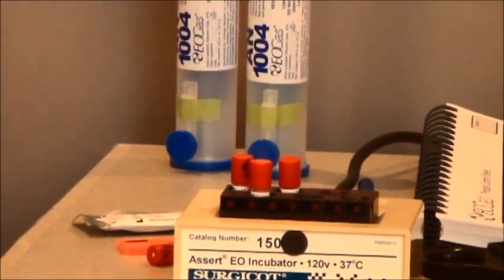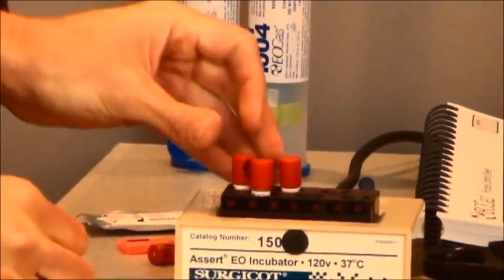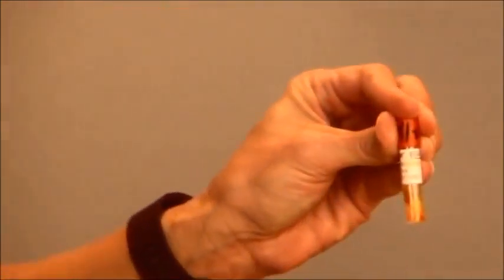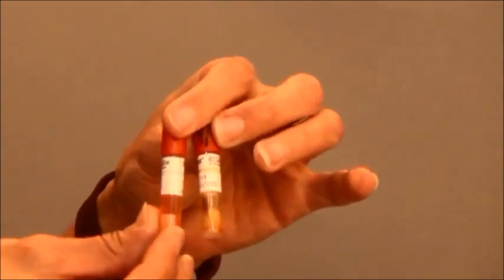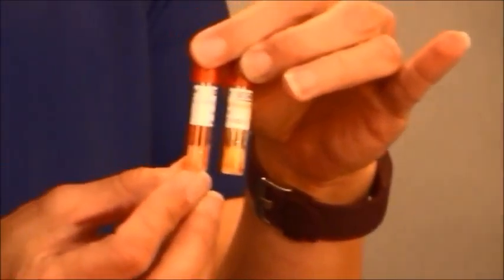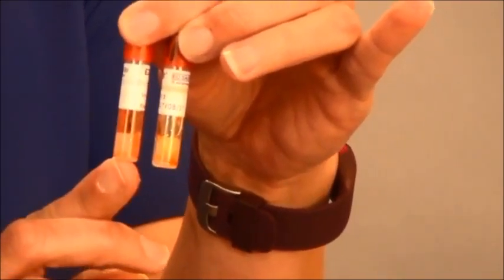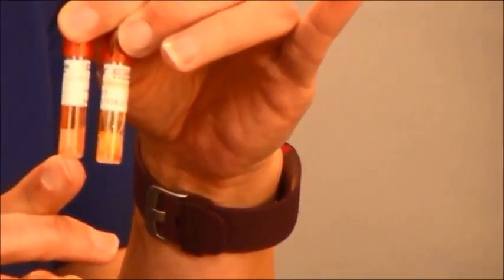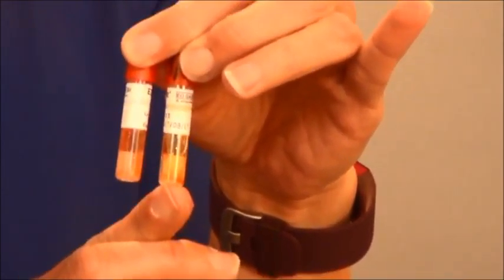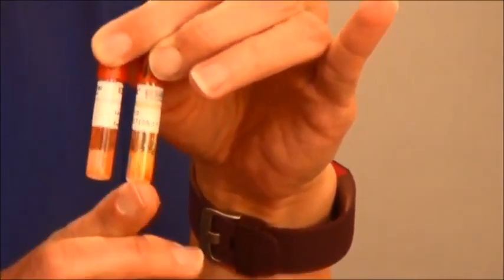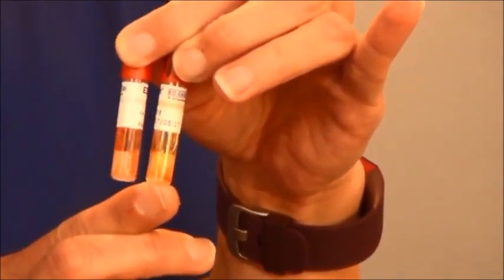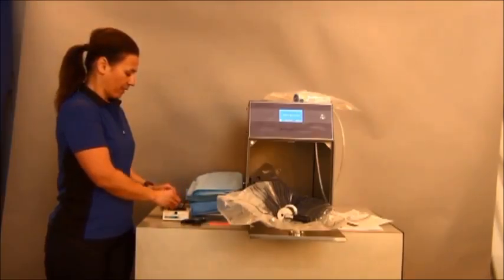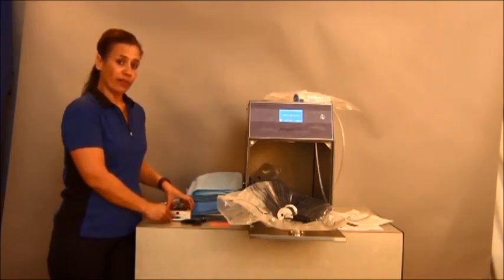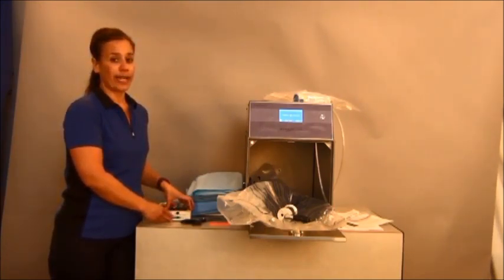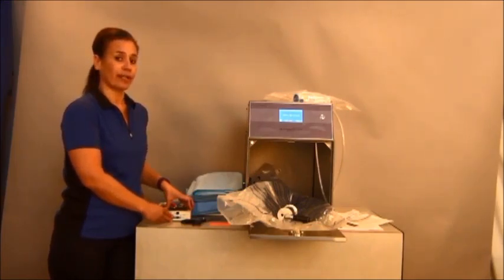You can check your biological indicators at the 24-hour mark, checking to see if there is any growth. As you can see by these two biological indicators, this one that has been run through a sterilization cycle has no color change at this point. The one that has not been run through a sterilization cycle has changed to an orange, somewhat rusty color. If you see no changes whatsoever, continue with the incubation process to 48 hours before releasing your products upon a successful read.